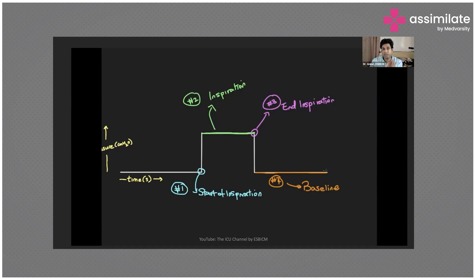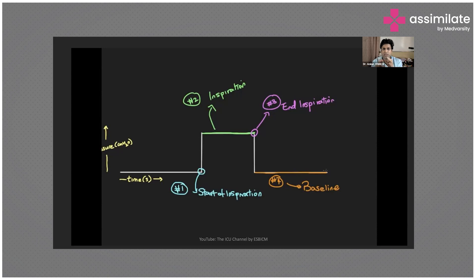The ventilator is a machine with no mind. Something has to tell the ventilator to give a breath to the patient — that is the trigger. At the end of inspiration, something tells the ventilator to stop inspiration so that exhalation, which is a passive process, can follow — that is the cycle. In between the trigger and the cycle, there is a pattern by which the ventilator delivers the breath, called the target or limit. So the whole ventilator game revolves around three variables: trigger, target or limit, and cycle.